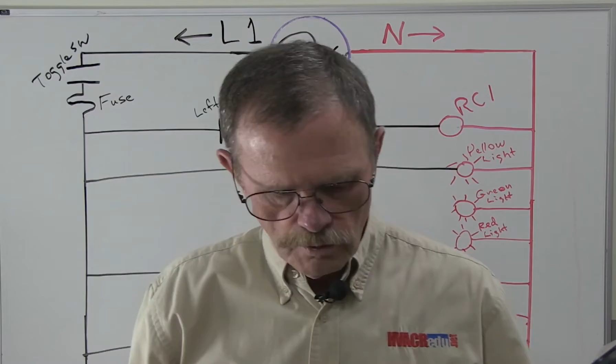It's one side of the relay coil. Let's chase through the coil. We've got the 24-volt circuit to one side of the load. We come back, come up here, and where does it go? It goes to one side of a switch. We'll stick that switch on the right-hand side. So I go to one side of the switch, comes out the other side, comes to here. And where does it go from there? Easy, goes right back to the secondary side of the transformer, as you can see right here. So I've chased that load out.